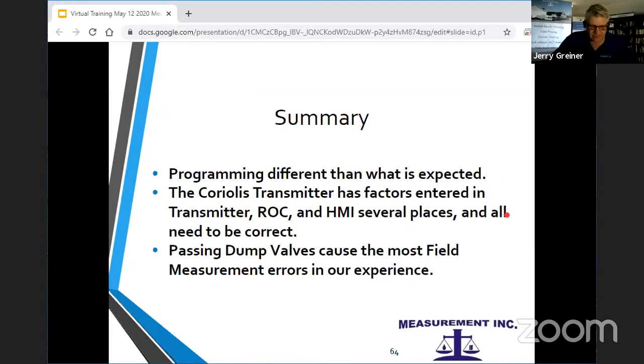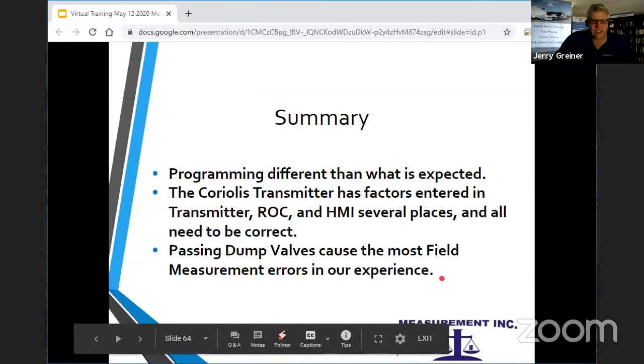And then finally, passing dump valves. They cause the most field measurement errors in our experience. Like I say, about 1 in 10 of the field proofs we do, we'll find that when we get looking. So watch your dump valves, verify your dump valves. If you're doing field proofs, you'll probably see that when you're there. You should check it. If you're pulling the meters out and doing a shop proof, they need to be checked as we go. And you'll find those things.